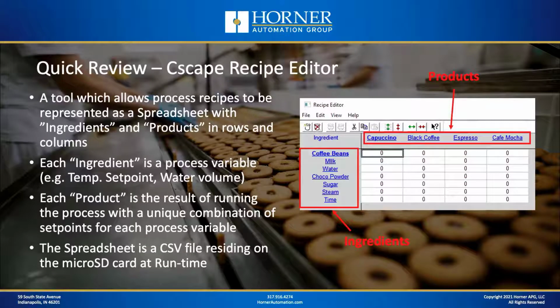So, quick review. The Cscape recipe editor is where a bulk of the setup for the recipe functionality is made in Cscape. Keep in mind that the recipe editor is a tool which allows process recipes to be represented as a spreadsheet with ingredients and products in rows and columns. Each ingredient is a process variable, like a temperature set point, a pressure set point, maybe a material quantity. Each product is the result of running the process with a unique combination of set points for each process variable.